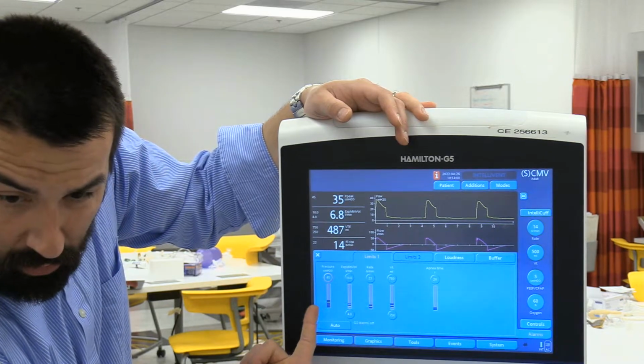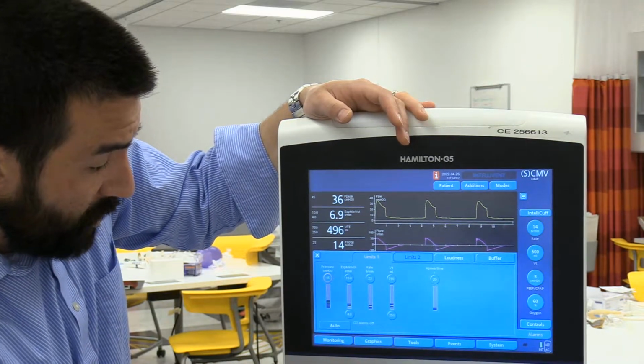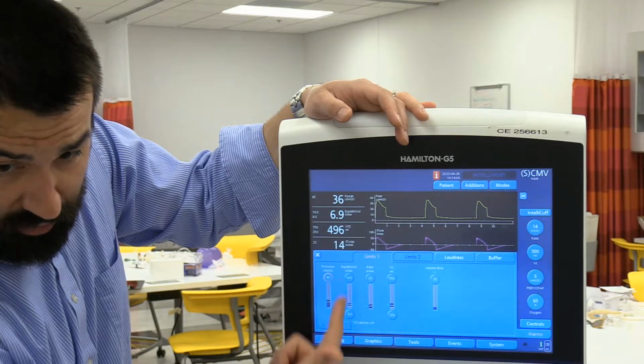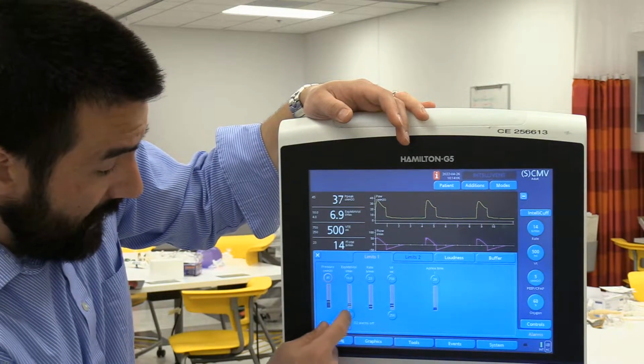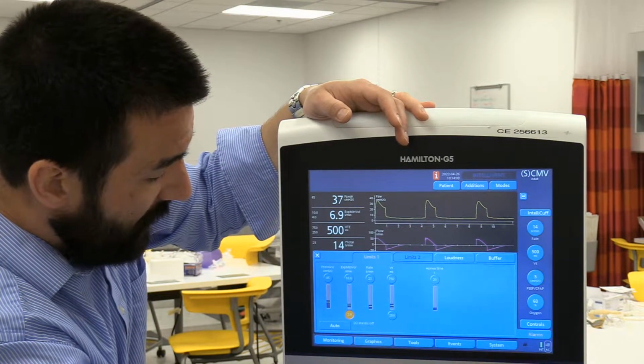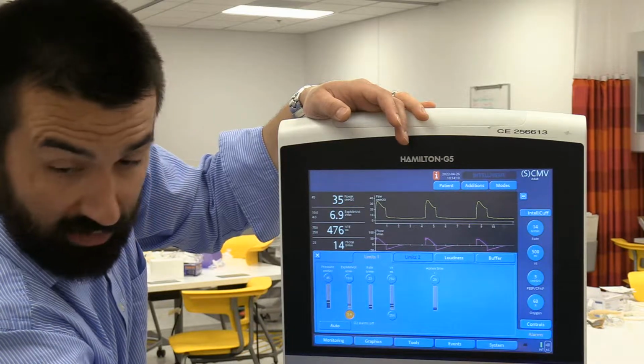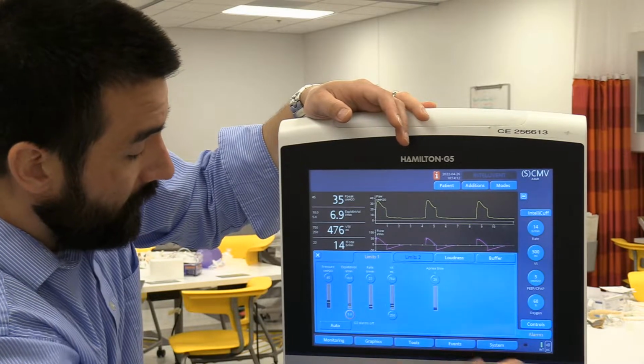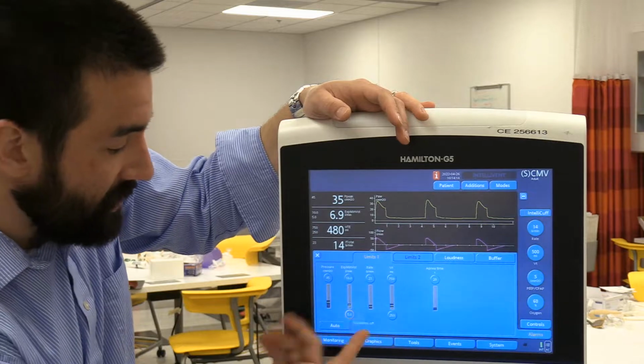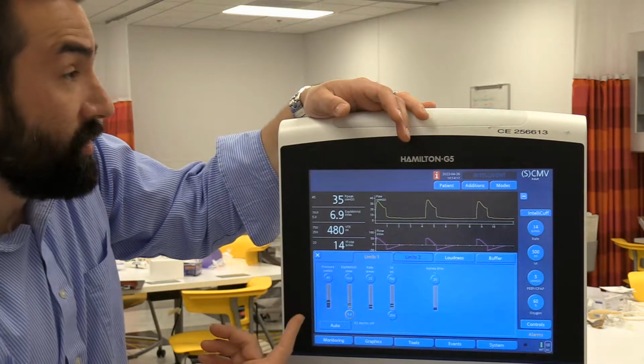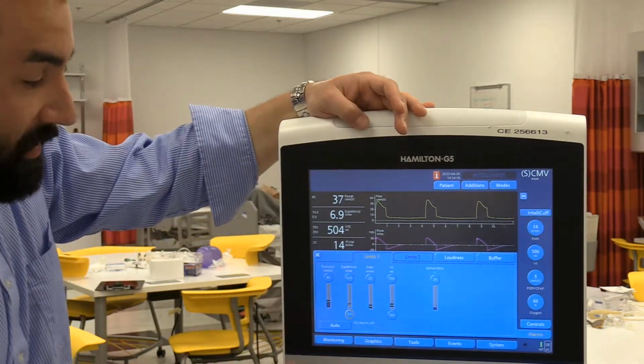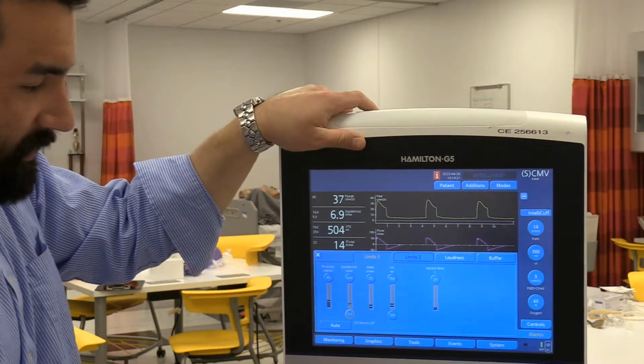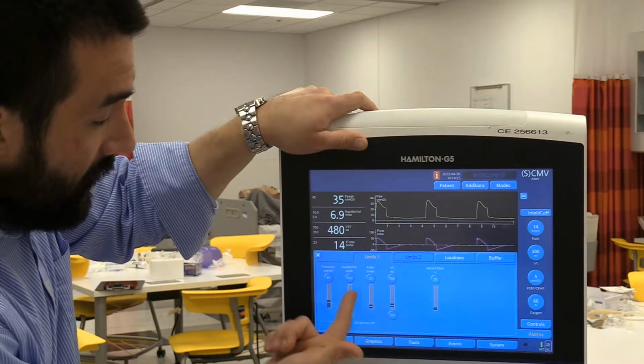Exhaled minute volume: if you look really close, there are little green dashes that show me where my current values are. The circles are where the alarms are currently set. Most patients, I'm not going to go too much lower than about 5 liters a minute for an adult. They're in mandatory ventilation right now in volume, so low minute volume shouldn't be any problem. But if you had a big leak or something like that, it might let you know.